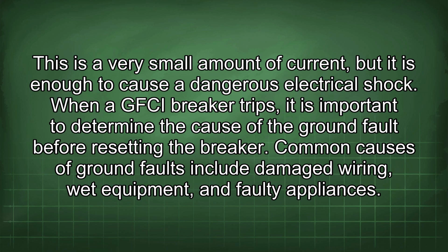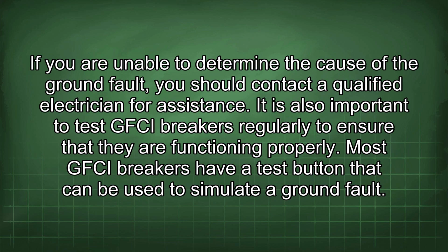When a GFCI breaker trips, it is important to determine the cause of the ground fault before resetting the breaker. Common causes of ground faults include damaged wiring, wet equipment, and faulty appliances. If you are unable to determine the cause of the ground fault, you should contact a qualified electrician for assistance.